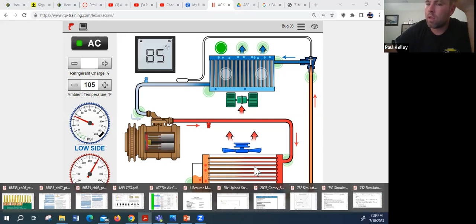Yep, definitely. If the TXV is stuck open, what does that cause? Equalized pressure - high, at least closer to equalized, right? The high side would be low and the low side would be high. We don't have that, so I think we can eliminate 1 and 4. Now we're left between 2 and 3.